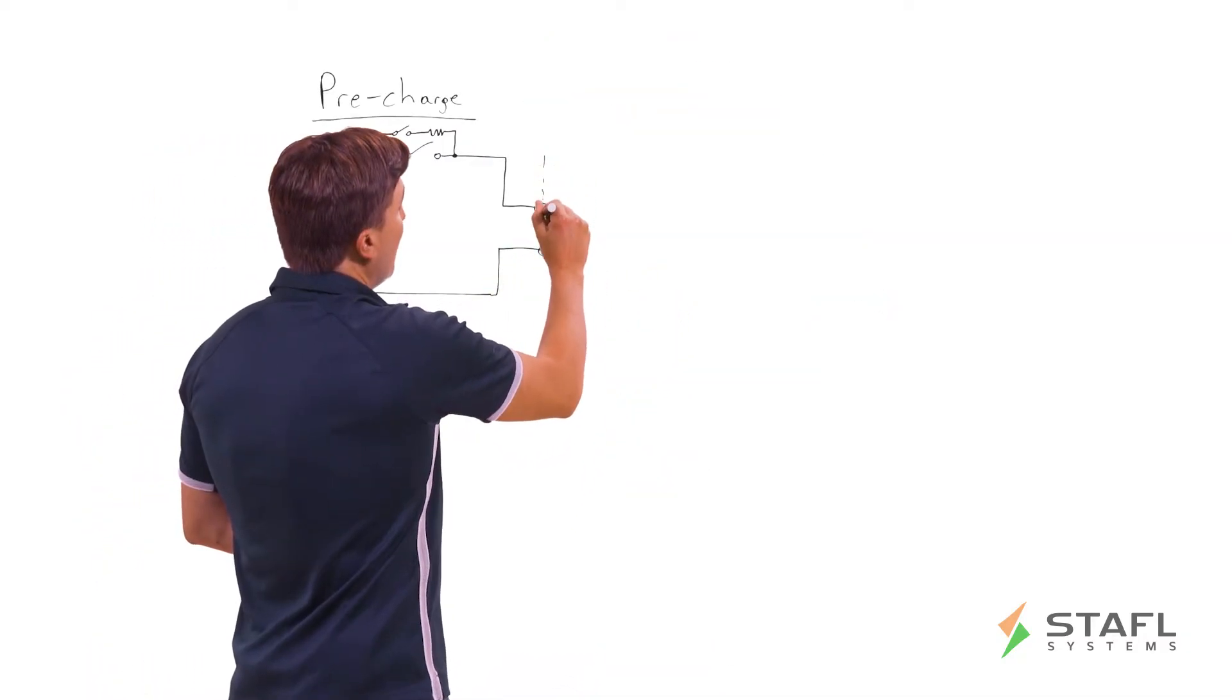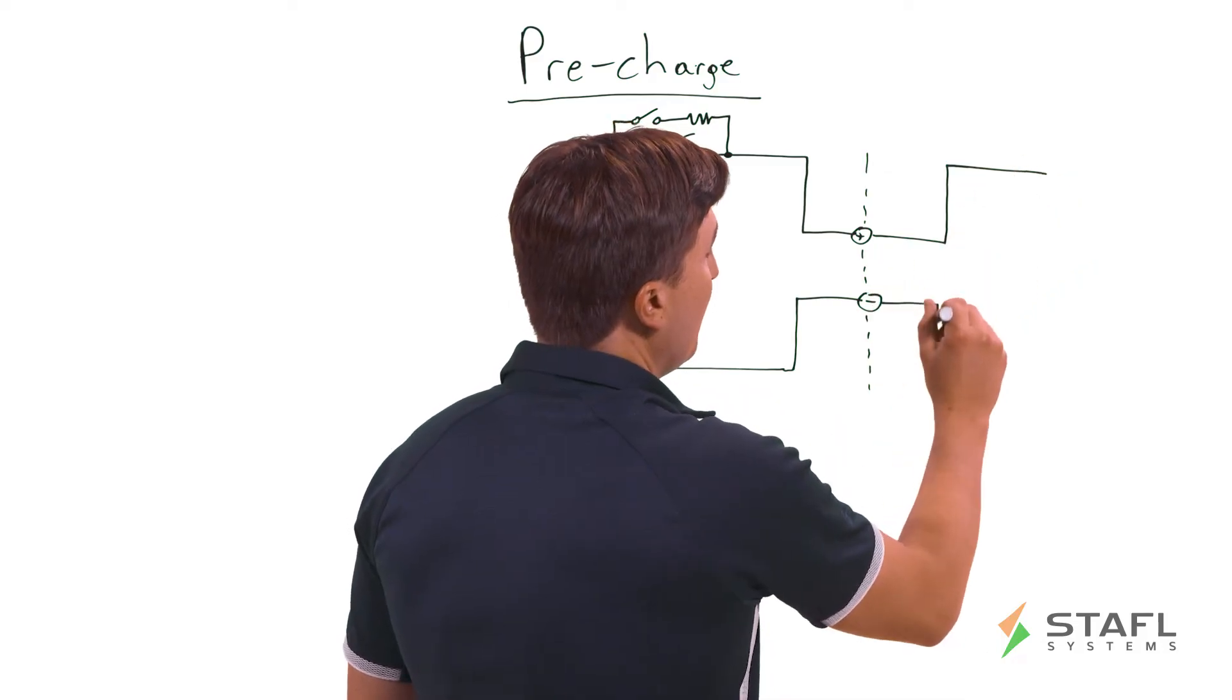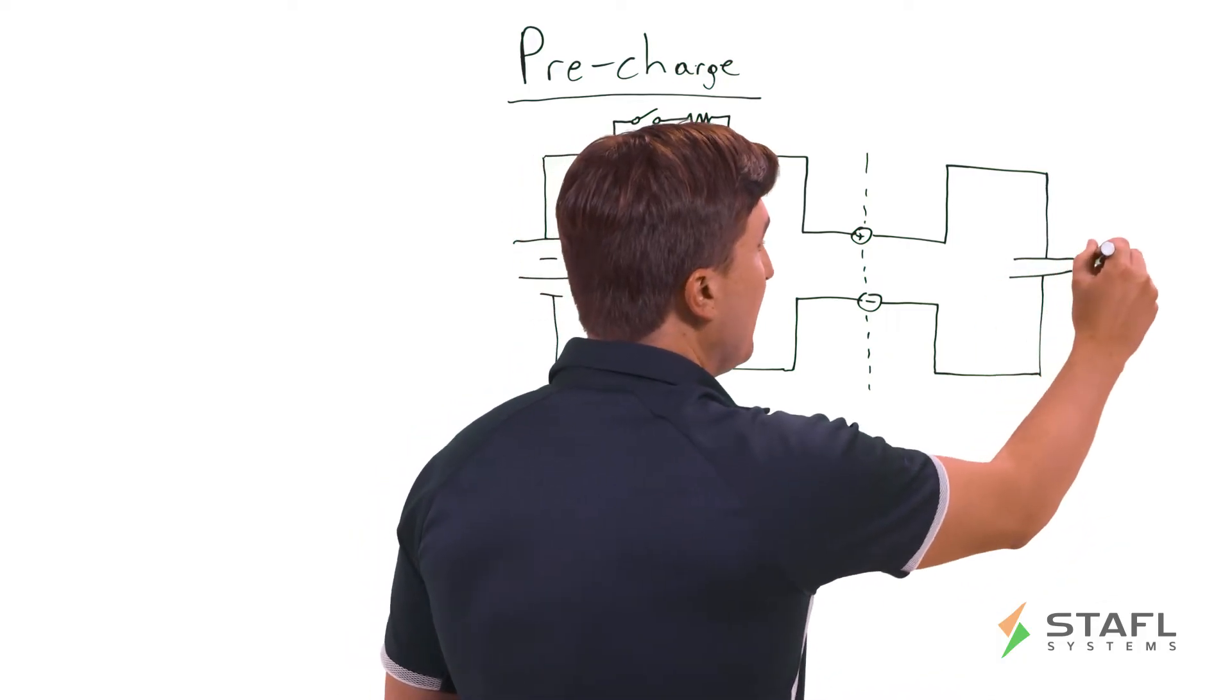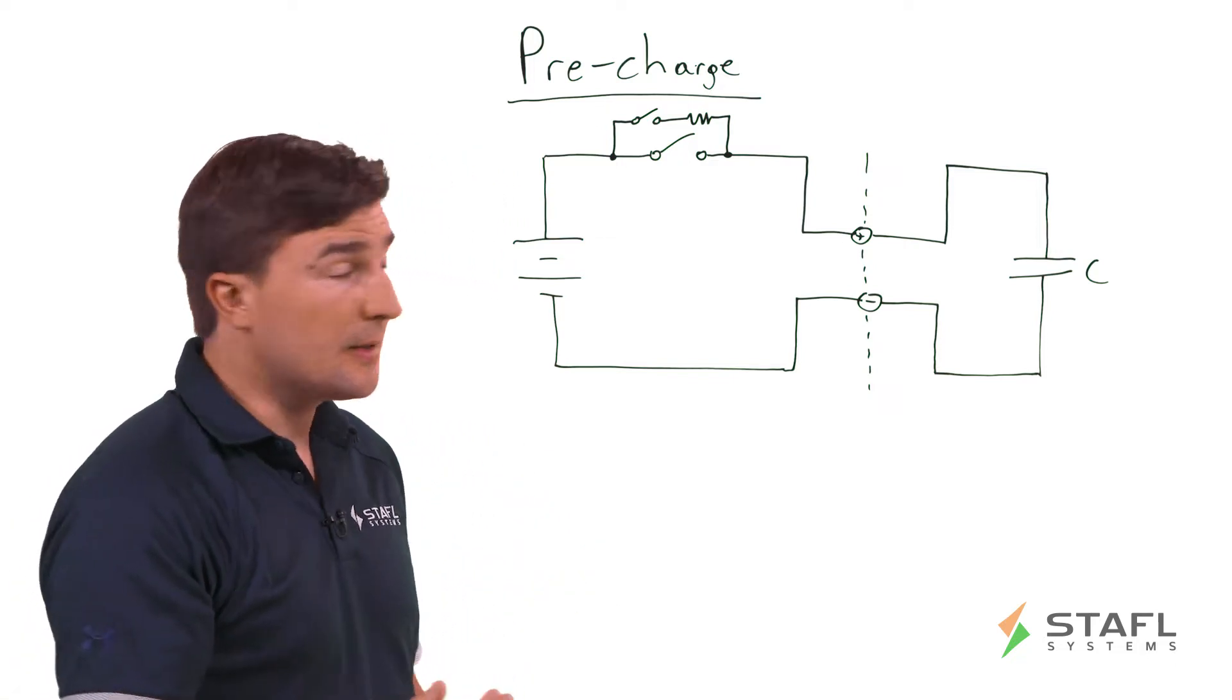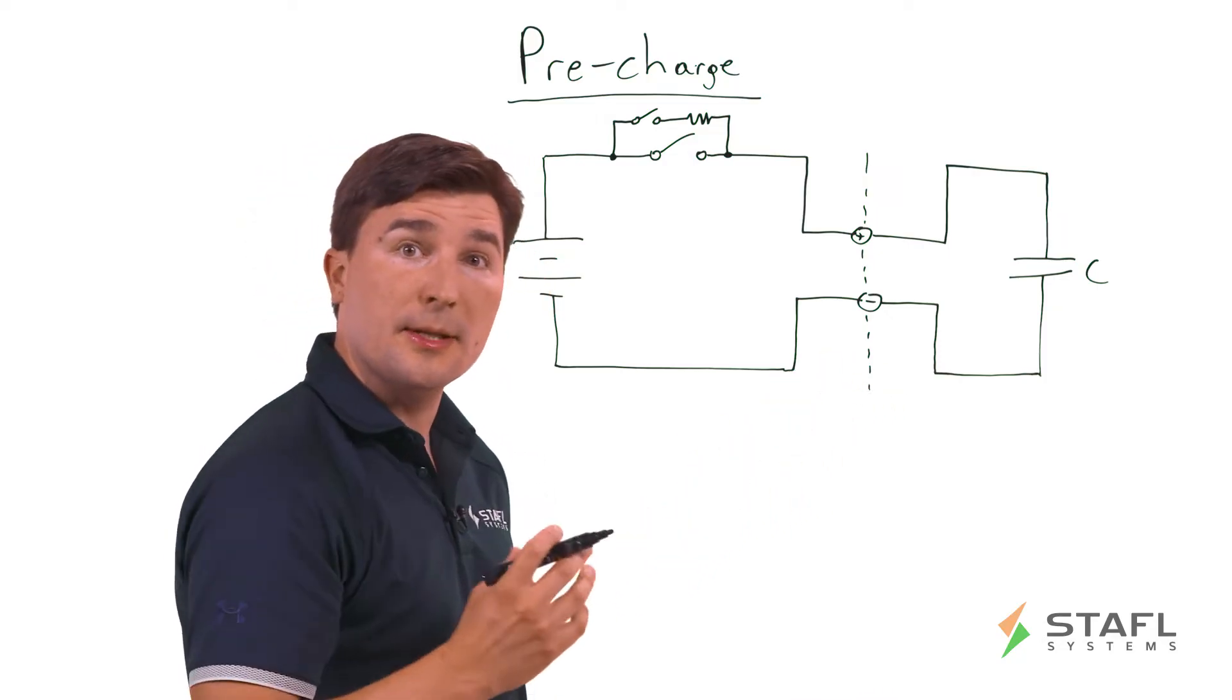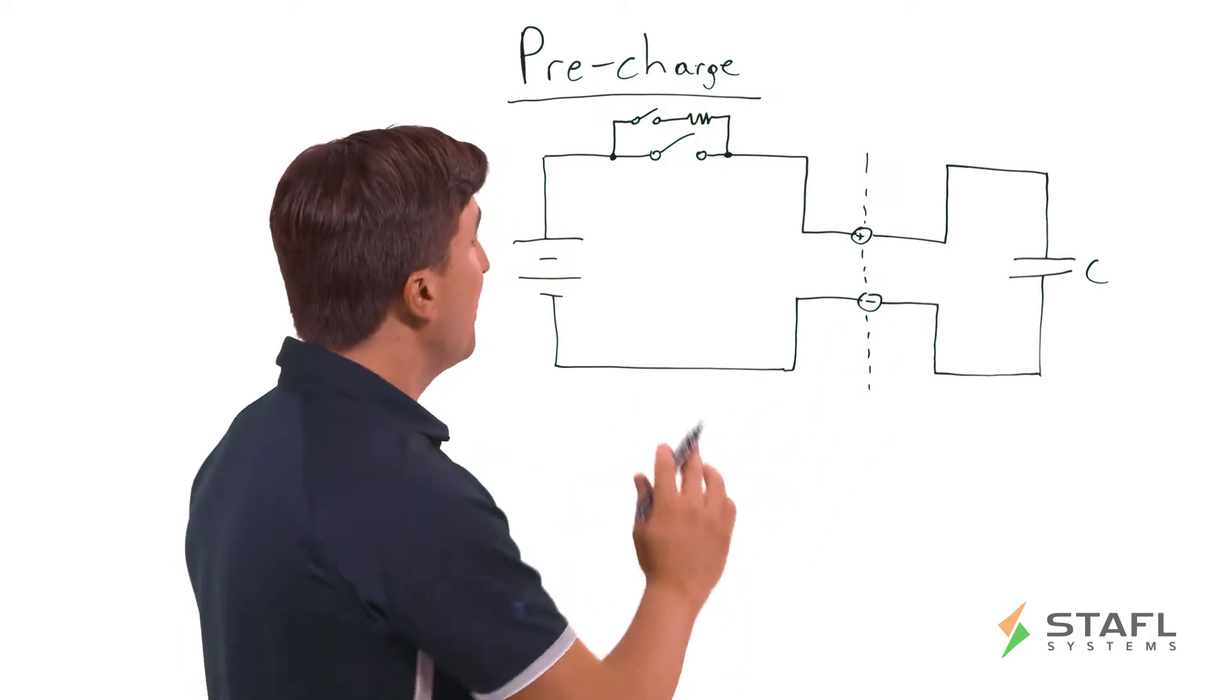So why is a pre-charge circuit necessary in the first place? Well typically it's because the external system connected to a lithium-ion battery pack has a rather large or significant capacitance. This can be a three-phase motor inverter, this can be a grid tie system for charging and discharging. There's a variety of power electronics and typically they have a filter capacitance for their high frequency switching. And this capacitance makes it absolutely necessary to have a pre-charge circuit.